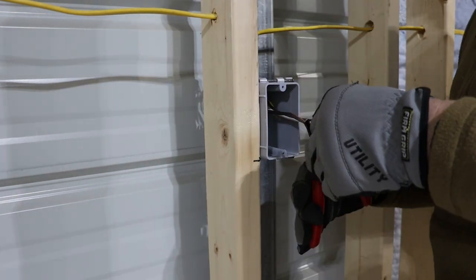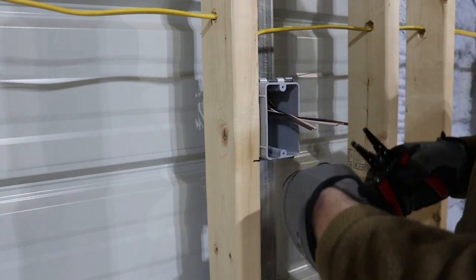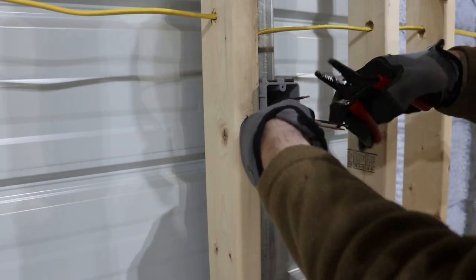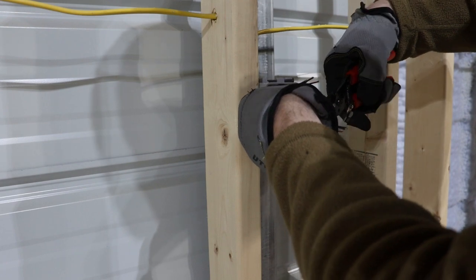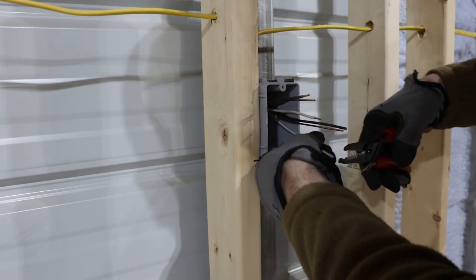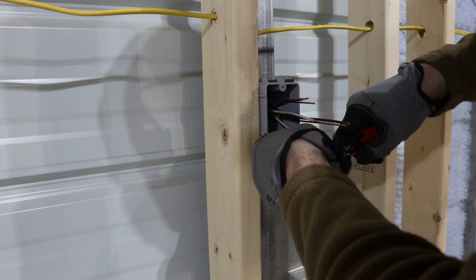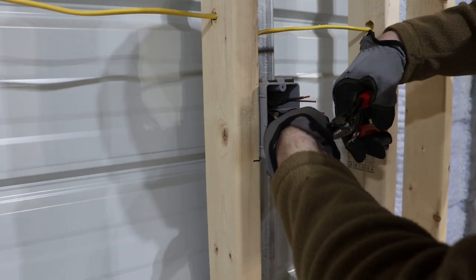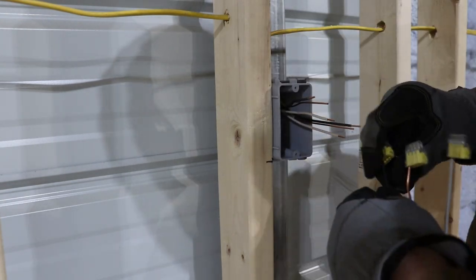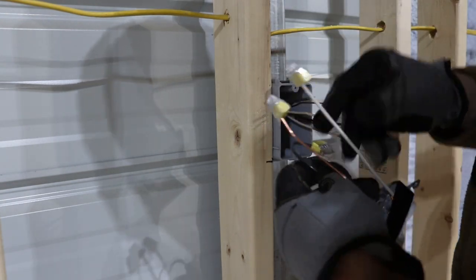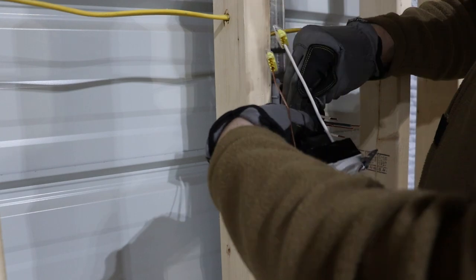You do want to make sure that these wires are pretty close to being the same length. Go ahead and strip these off. These ones are only three-eighths, about three-eighths of an inch, because you're not trying to wrap them around the screw or anything. You certainly don't want any copper sticking out of the back of the connectors or a wire nut if you decide to wire nut these.